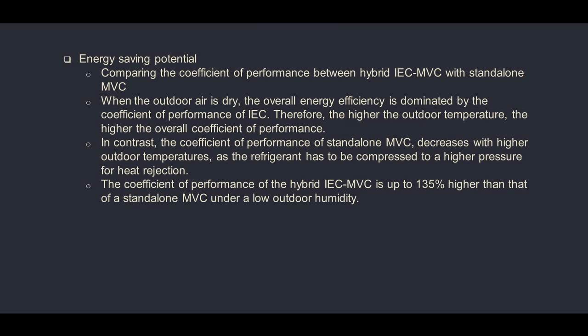Energy saving potential. Comparing the coefficient of performance between hybrid IEC MVC and standalone MVC. When the outdoor air is dry, the overall energy efficiency is dominated by the coefficient of performance of IEC. Therefore, the higher the outdoor temperature, the higher the overall coefficient of performance. In contrast, the coefficient of performance of standalone MVC decreases with higher outdoor temperature as the refrigerant has to be compressed to a higher pressure for heat rejection. The coefficient of performance of the hybrid IEC MVC is up to 135% higher than that of a standalone MVC under a low outdoor humidity.